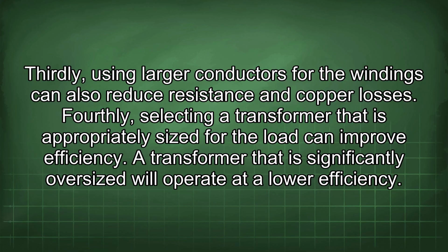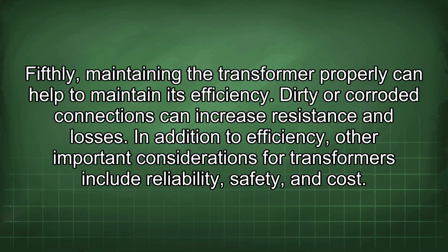A transformer that is significantly oversized will operate at a lower efficiency. Fifthly, maintaining the transformer properly can help to maintain its efficiency. Dirty or corroded connections can increase resistance and losses. In addition to efficiency, other important considerations for transformers include reliability, safety, and cost.